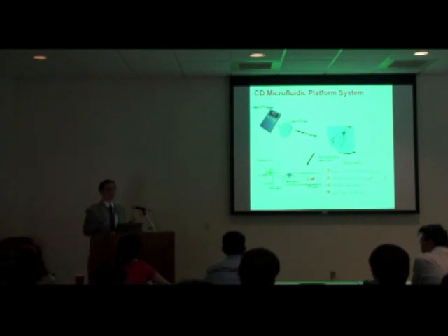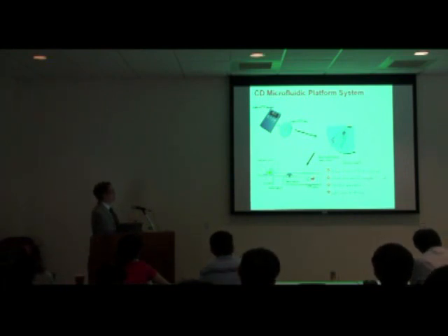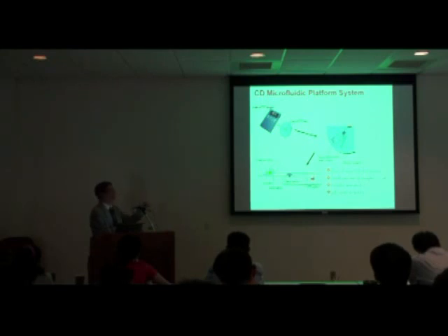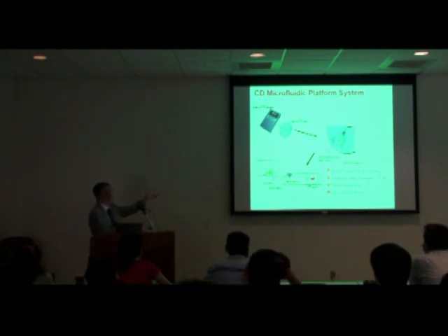When it's ready to use, the user can put a sample usually near the center of the CD and basically rely on the rotation. Very simple. Because rotation gives you the centrifugal force, and that's your pump. And that will drive the samples and the reagent to the detection area one by one. Remember, ELISA needs to be done one by one. So we rely on the rotation to do that.